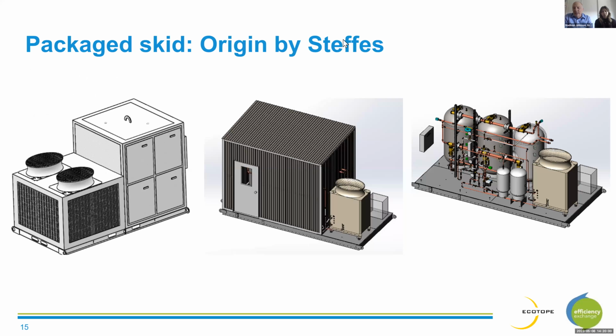This is what the fully pre-packaged system looks like. On the far right there is kind of an exploded view of what's inside the skid. It includes the heat pump, the primary storage tanks, expansion tank, heat exchanger and pump assembly, controls and all the valving. In the center there is a picture of what this first iteration looked like that was delivered to this building. It's almost like a little pre-manufactured mechanical room adjacent to the heat pump. And on the far left is where Steffes is evolving the design in the future, with a smaller and more optimized footprint.